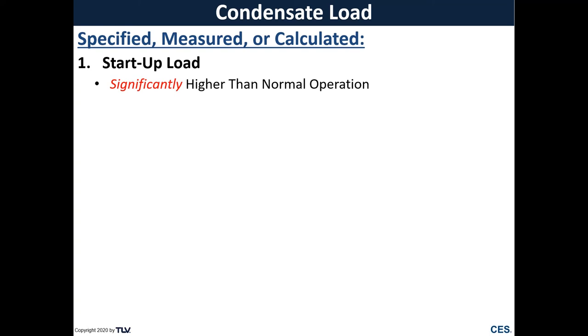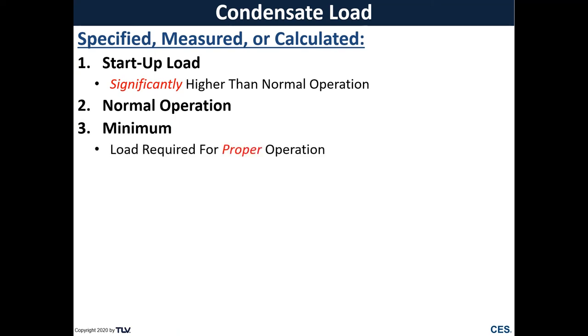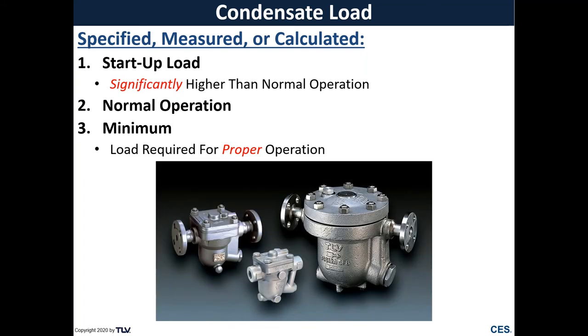That can be significantly higher than what we would typically see during normal operation of that steam trap, because we have a large mass of pipe and equipment that needs to be heated on startup, so that's going to require a significant amount of condensate to condense to get that up to temperature. Next is our normal load, what we would expect to see during steady state or normal operation. And with some steam traps, we might also need to consider, what is our minimum condensate load? Some steam traps may require a minimum flow rate in order to operate properly. So these things can all affect what our steam trap sizing will look like.